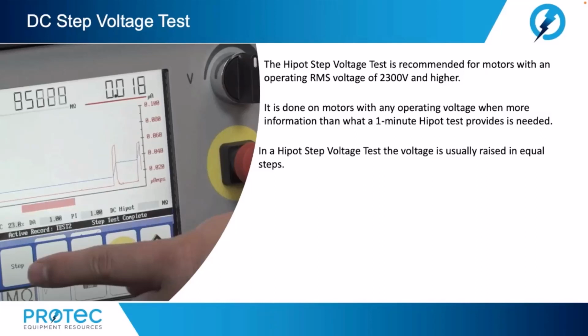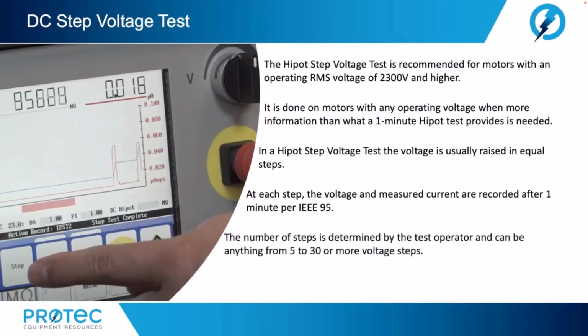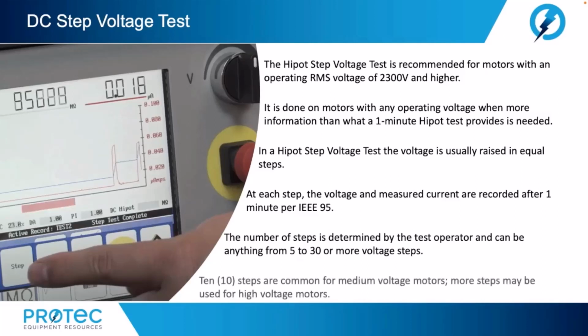the voltage is usually raised in equal steps. At each step, the voltage and measured current are recorded after 1 minute per IEEE 95. The number of steps is determined by the test operator and can be anything from 5 to 30 or more voltage steps. 10 voltage steps are common for medium voltage motors. More steps may be used for high voltage motors.